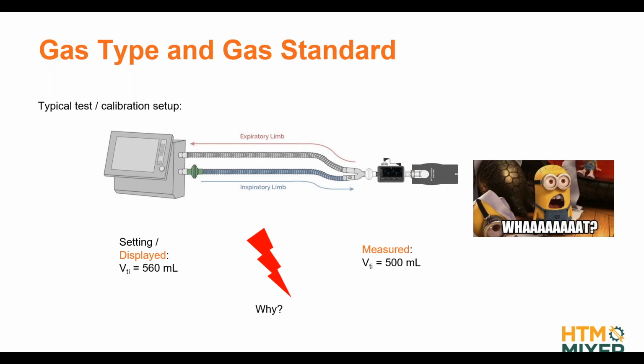Yeah, now we are comparing two different gas standards, right? We are comparing volume in milliliters, but in two different gas standards. The 560 is BTPS on the ventilator, but I assume in this example that our analyzer is set to ATP, actual temperature and pressure, and then we have quite off measurements here, right?